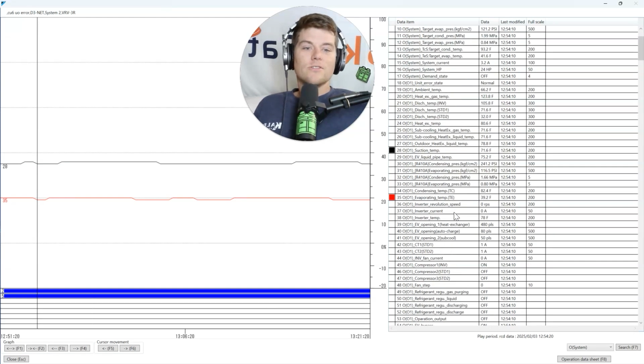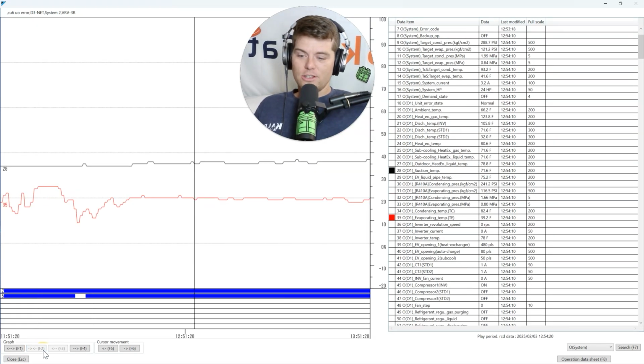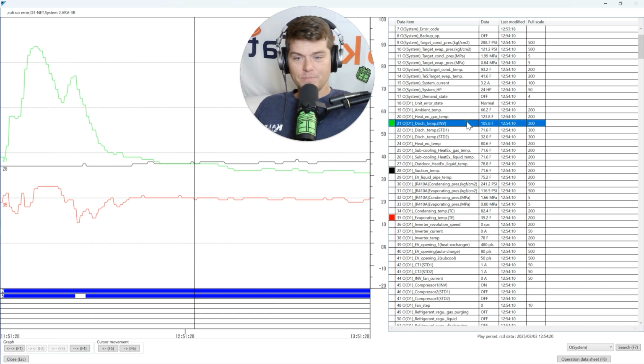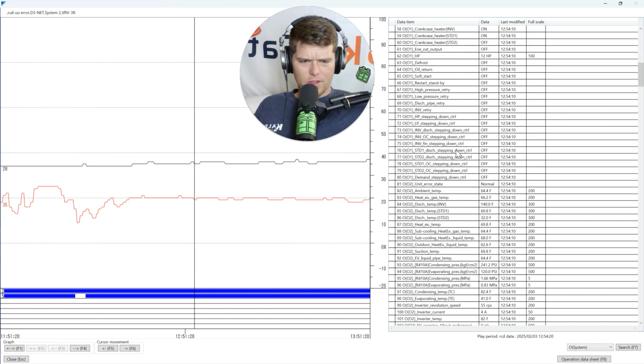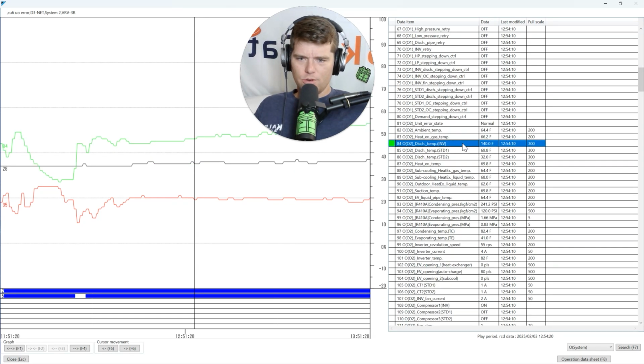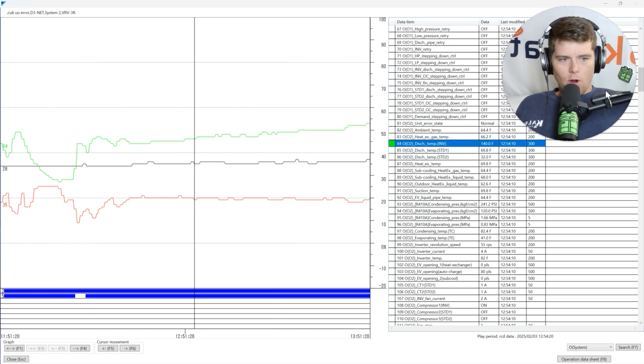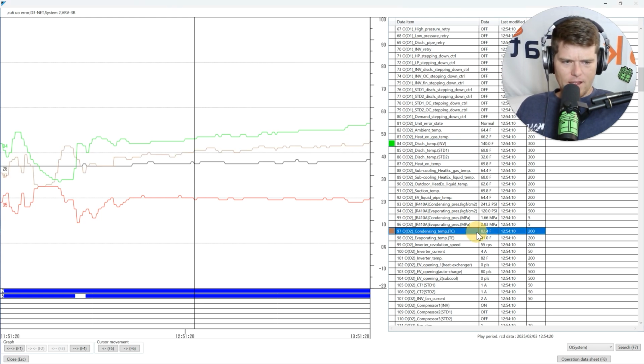You're missing it. So let's go back to our little thing here. Let's go back to the 2 hours. Okay. Even in 2 hours, what did that look like? We could go back and we could populate the same things again. Let's see here. I'm in the wrong module. Let's go back to the other module. Move my big old head out of the way here. Okay, it goes up a little bit, but even in a 2 hour window of troubleshooting this data, if we do both TC and TE, and we look at our discharge temp, okay, we got 82 degrees to 140, right?